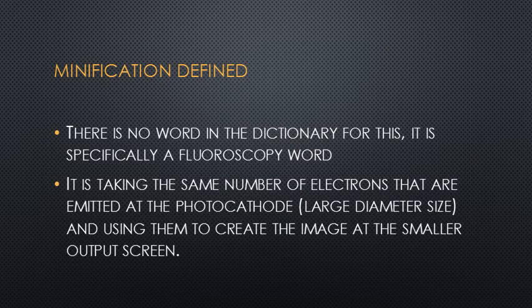Minification is interesting — there's actually no word in the dictionary for it, but it causes the image to be brighter because there's the same number of electrons producing the image. Most image intensifiers have diameters of 6, 9, or 12 inches, and output screens are about 1 inch. These diameters are usually stated in centimeters: a 6-inch screen is 15 centimeters, a 12-inch screen is 30 centimeters, and output screens are 2.5 centimeters.